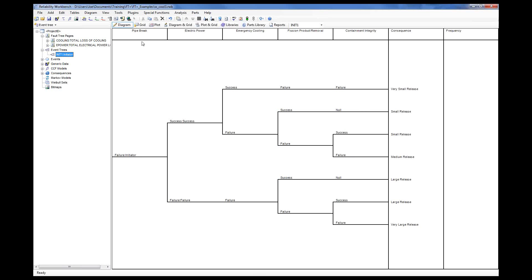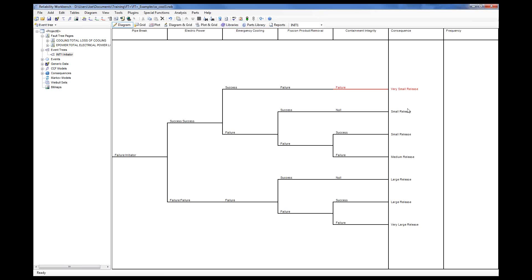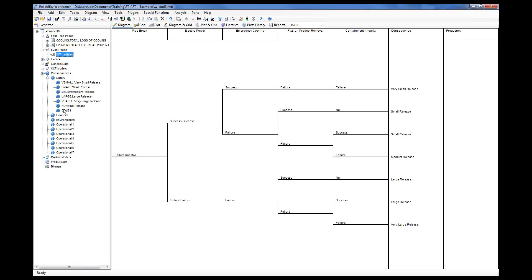We can do that for every column, including the initiating event — that's where we get the bow tie event, where the fault tree quantifies the initiating hazard of the event tree. The emergency cooling system column is also quantified by a fault tree gate. The consequences node — which fault tree users may have noticed in the project hierarchy and wondered about — has to do with event trees. The program supports up to ten different consequence categories; you can track safety, financial, or environmental consequences, and assign one consequence from each category to a final branch in your event trees.